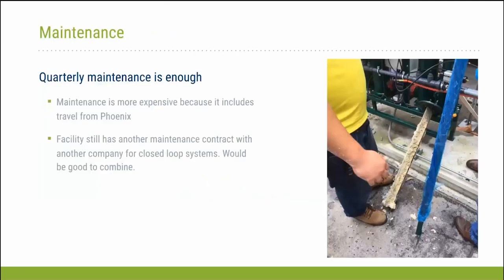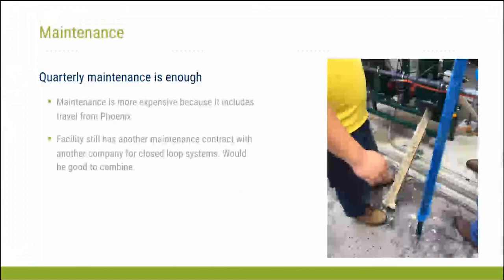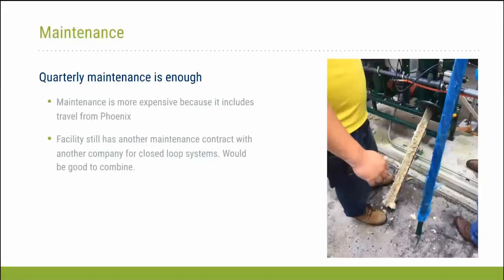The vendor is located out of Phoenix, and so for us, the maintenance cost was a little over $6,000, I believe, for a one-year maintenance contract with 4 visits. And I know that the incoming water quality is different in different parts of the nation, and where this vendor is located out in Phoenix, they often see very high incoming hardness, over 1,000. And even with that, this is what I'm told, they've been able to run COC readings of 10 to 15 with incoming water in the range of 1,000 to 1,500 microsiemens or TDS hardness, okay?